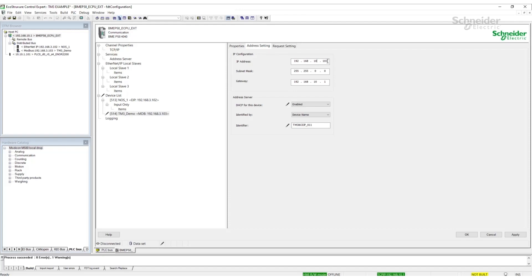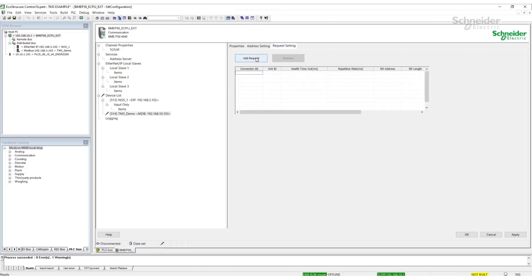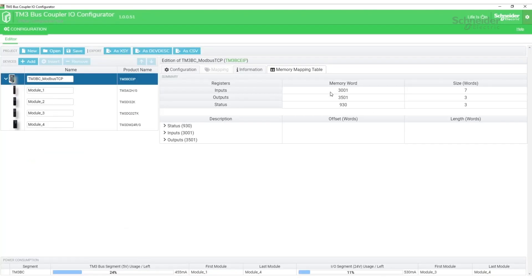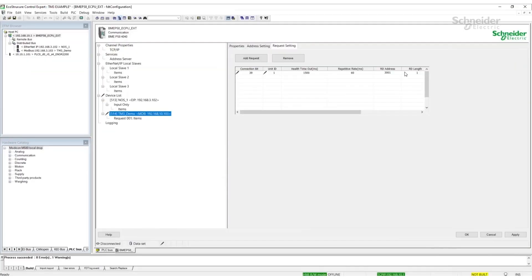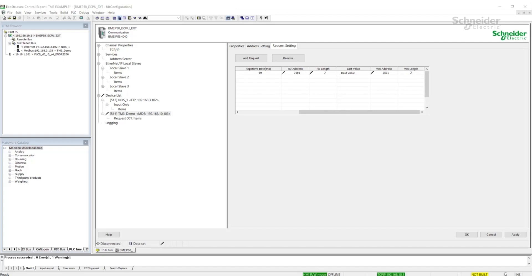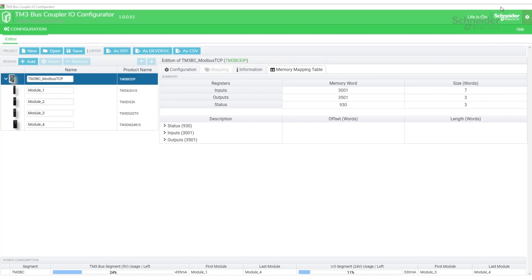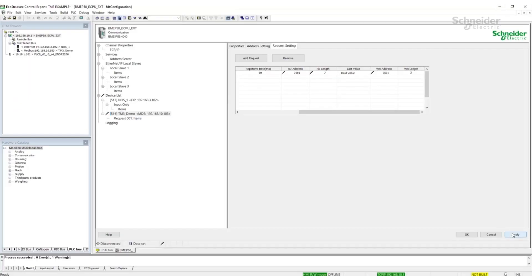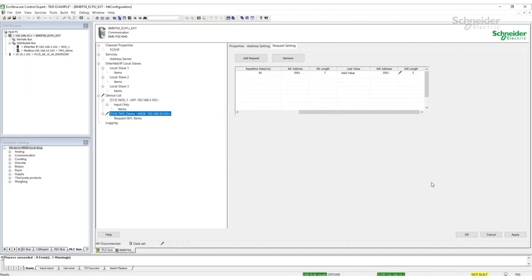The next step is to create the Modbus request for the read and write data to the bus coupler. We'll add request, change the unit ID to 1. The read address we will set to match the configuration. Pulling up the bus coupler, the memory word start is 3001 and size of words is 7. We'll do the same for the writes. The write address was 3501 with the length of 3. Now that this has been configured, we can apply the changes, close the dialog box and accept.